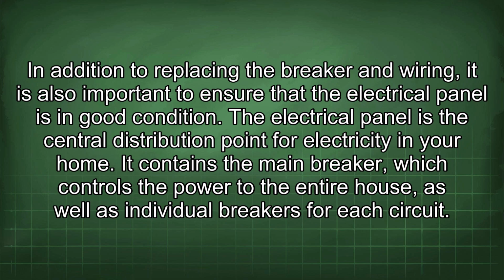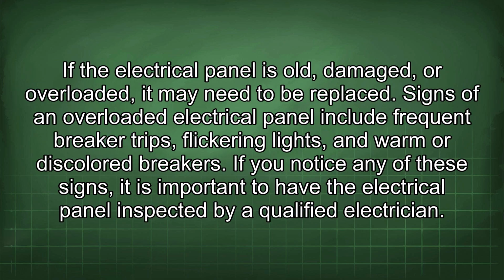In addition to replacing the breaker and wiring, it is also important to ensure that the electrical panel is in good condition. The electrical panel is the central distribution point for electricity in your home. It contains the main breaker, which controls the power to the entire house, as well as individual breakers for each circuit. If the electrical panel is old, damaged, or overloaded, it may need to be replaced. Signs of an overloaded electrical panel include frequent breaker trips, flickering lights, and warm or discolored breakers. If you notice any of these signs, it is important to have the electrical panel inspected by a qualified electrician.